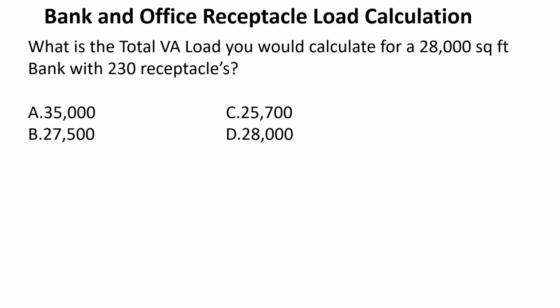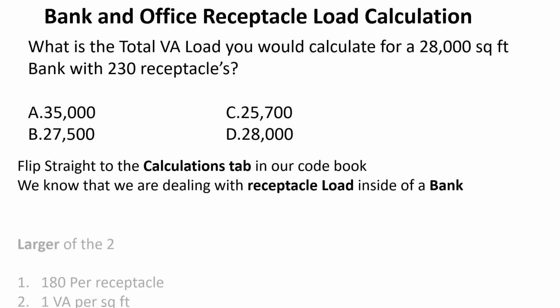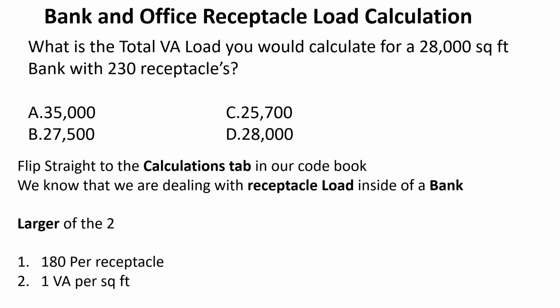Let's do another one. What is the total VA load you would calculate for a 28,000 square foot bank with 230 receptacle yokes? So we flip straight to our calculations tab in our codebook. We know that we're dealing with receptacle loads inside of a bank. We're going to select the larger of the two, either 1 or 2: 180 VA per receptacle yoke or 1 VA per square foot.